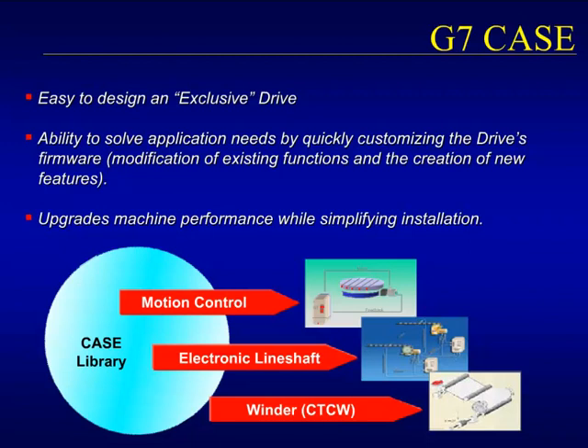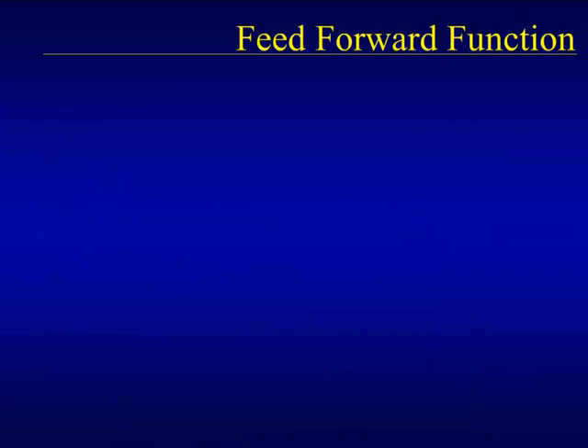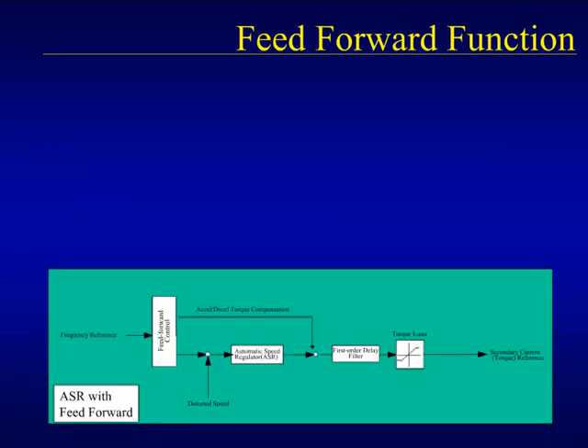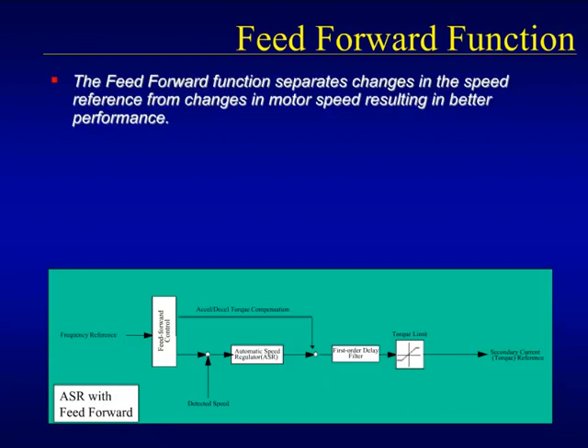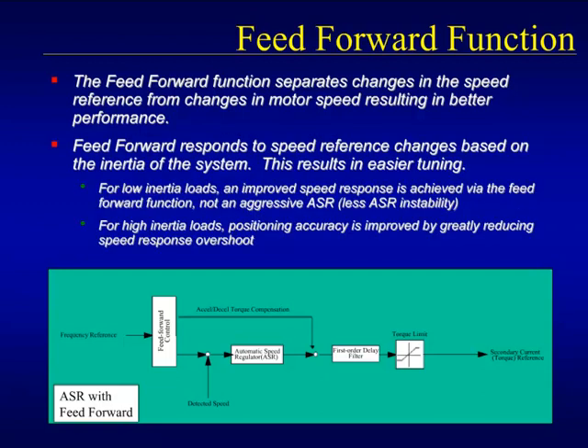and automotive industries. Another feature found only in the G7 is the feed-forward function. The ASR, or automatic speed regulator circuitry, is a PI function that regulates drive output to achieve accurate speed regulation. The feed-forward function will isolate the ASR's reaction to motor speed errors caused by frequency reference change from reactions to motor speed errors caused by the load changes. By separating the two types of motor speed errors, the ASR with feed-forward can more effectively compensate for the errors without the use of overly aggressive ASR gains.